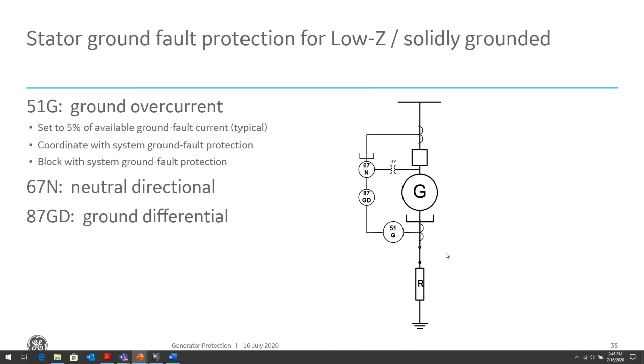And again, these types of protection will be able to protect for the majority of ground faults, except for faults right at the neutral of the generator. And in that case, do you really need to detect those faults? Because with zero ground fault current, it's almost like having a solidly grounded generator anyway. So not a concern.